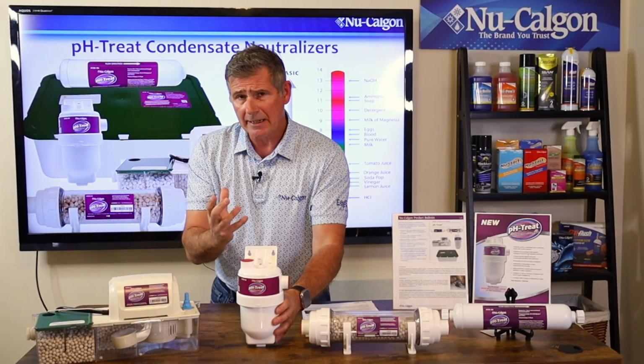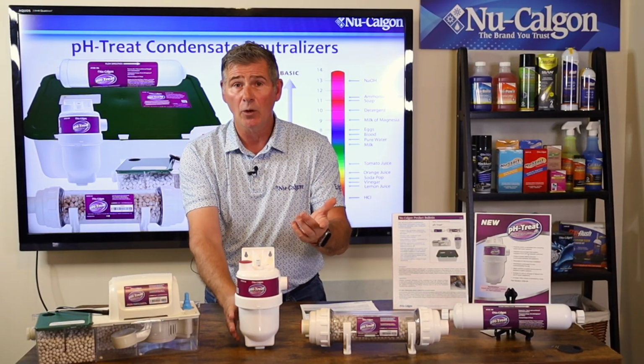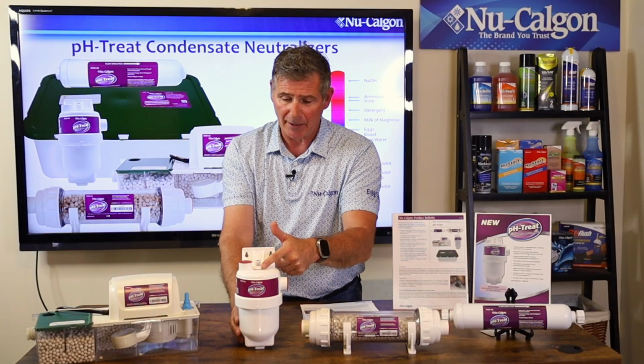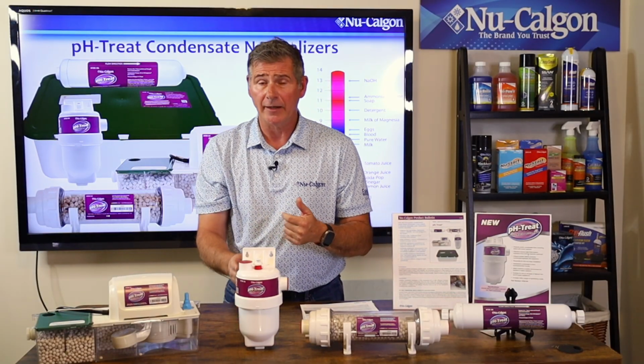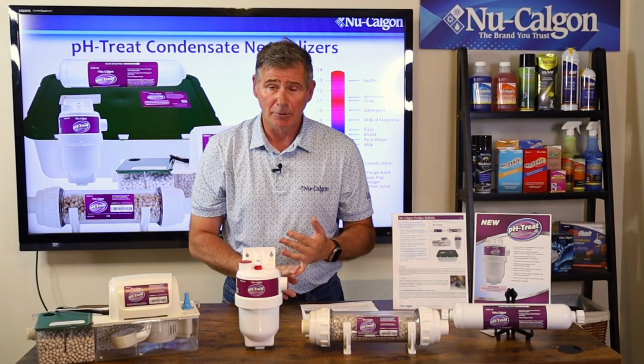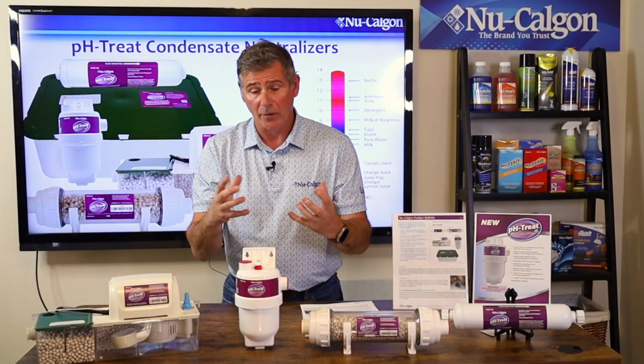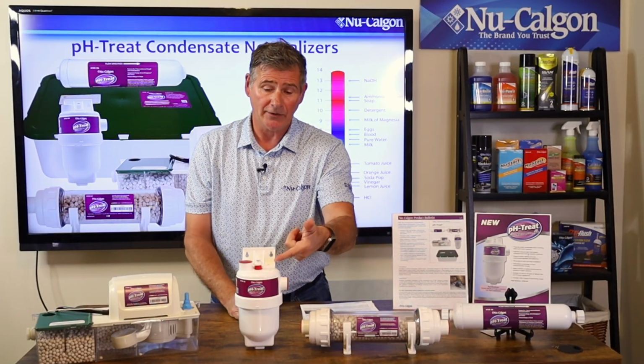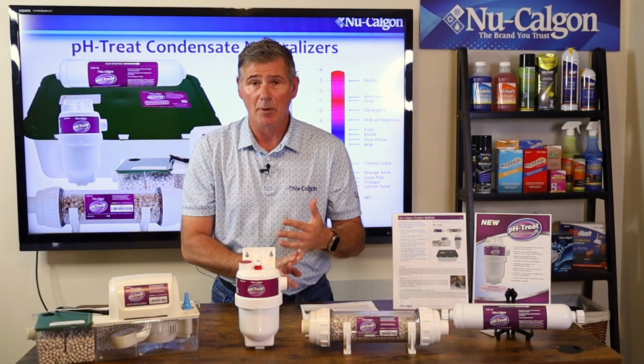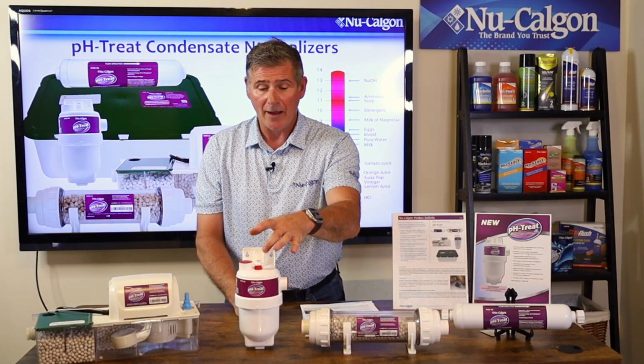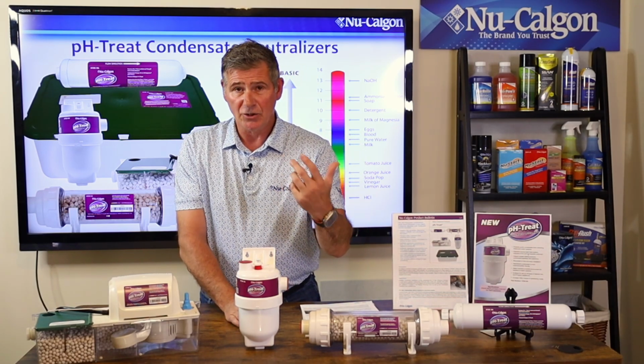And what's really nice with this is it has a manual float on the inside. You can see I'm just going to pop it up here. That's going to let you know that you may have some type of blockage inside the unit itself, or the media is coming up and causing that float to rise up. So either the media is probably no longer usable, or you have some type of blockage in there, to let you know that there is an issue.